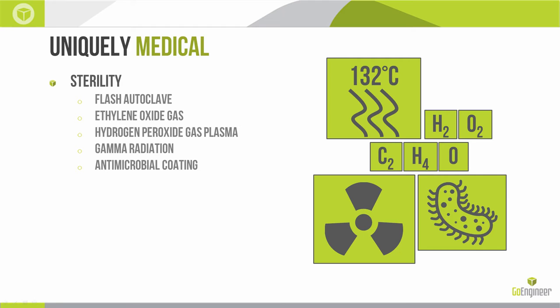Ethylene oxide gas (ETO) sterilization using Anprolene AN74i on a 12-hour cycle achieves a 100% success rate. Hydrogen peroxide gas plasma on a Sterrad machine at 55 minutes, max temperature 55°C, transporting parts in Tyvek pouches — again 100% sterilization success. Gamma radiation works fine with FDM and the biocompatible Med610 materials on the PolyJet side. Antimicrobial coating was new in my research: Stratasys studied commercially available water-based antimicrobial coatings and showed a 99.9999% reduction in bacterial growth, a 5-log reduction. We have a lot of different sterilization options if you need sterile parts.